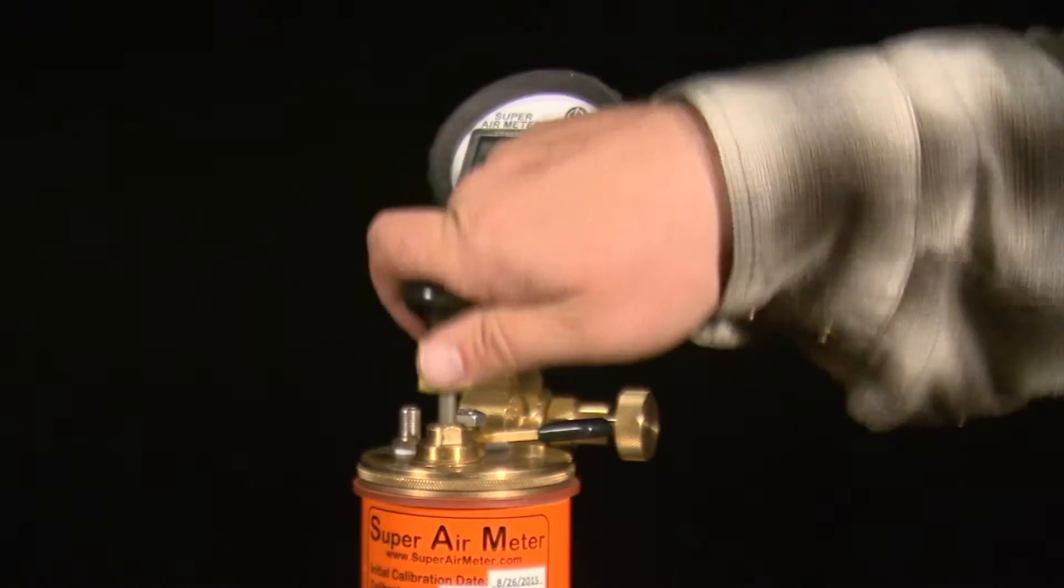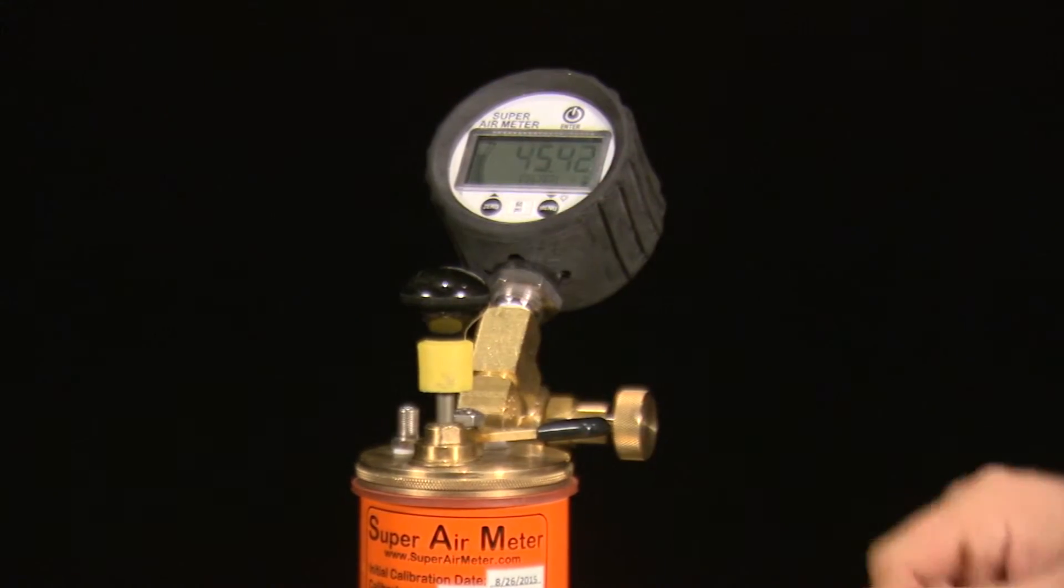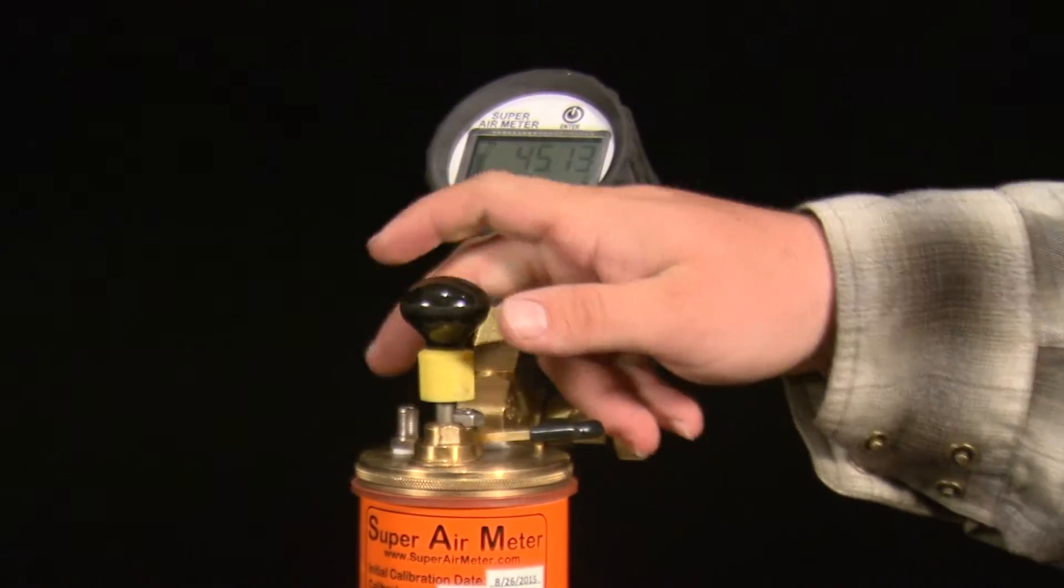After 20 minutes, if the pressure is still right around 45, then you know the top chamber is not leaking and you've installed it correctly.